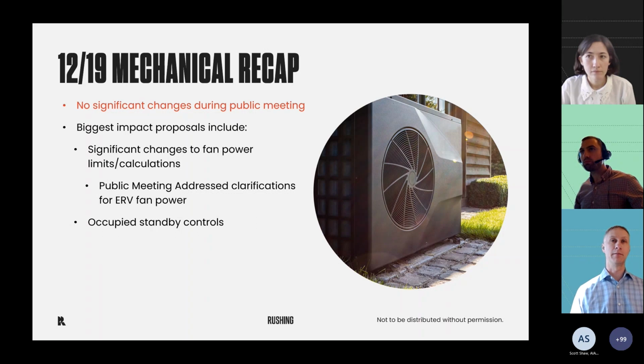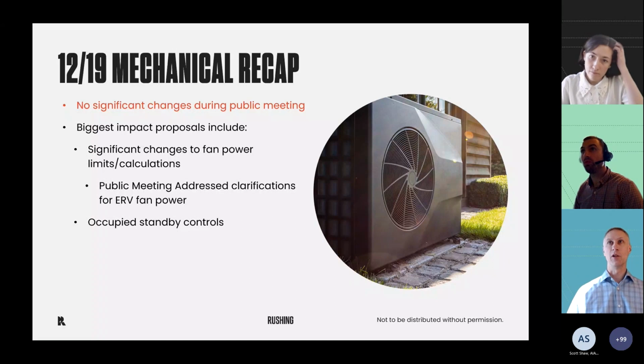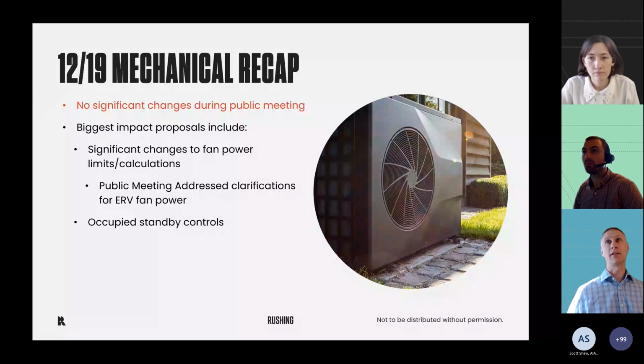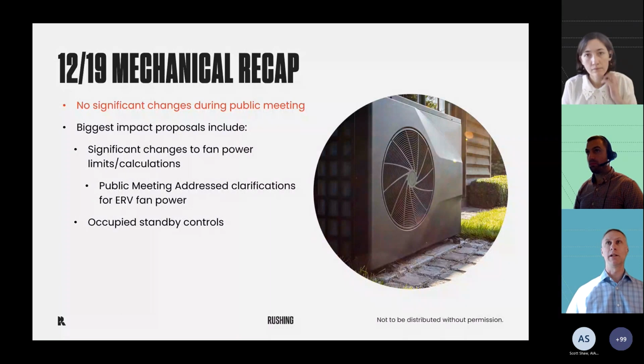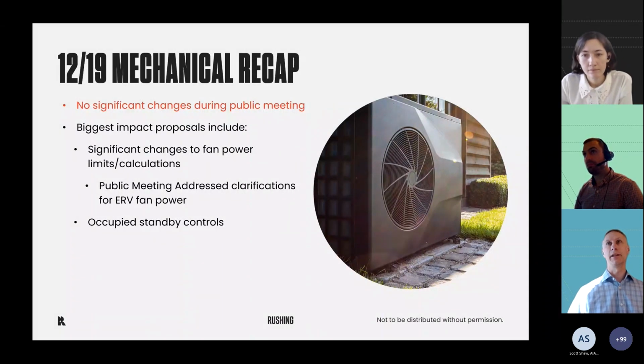The control zones are essentially set up by floor and/or by a maximum of 25,000 square feet. So if you had a 50,000 square foot floor plate, you would have two zones, and as each zone becomes unoccupied, you'd be setting back the space temperature set points. As all the zones within that floor or 25,000 square foot space become unoccupied, you'd be required to shut off the ventilation systems, both the outdoor air supply and the associated toilet exhaust. It's a good proposal for energy savings, but it adds complexity in using occupancy sensors to set back and reduce ventilation values.